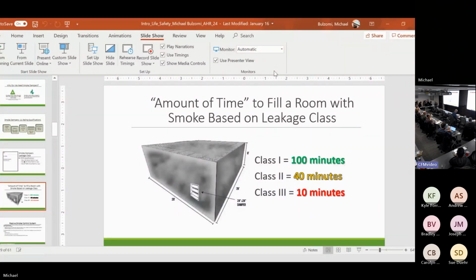This room was 20 foot by 20 foot with an 8-foot ceiling, and had a 24 by 24 ducted smoke damper that was closed, and there was smoke pouring through that duct. If it was a class 3 leakage rated damper, this room would fill up with smoke in 10 minutes. Well, let me put this statement out there. Do not quote this. Do not go tell somebody that a class 1 damper gives you 100 minutes of protection. This is hypothetically speaking, so you understand the scale of difference in leakage between class 3, 2, and 1. Okay? Class 3, this room will fill up in 10 minutes.